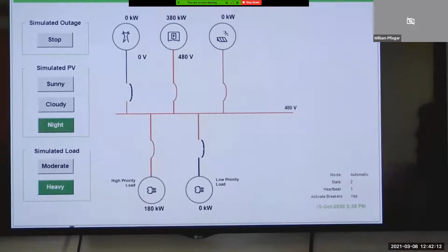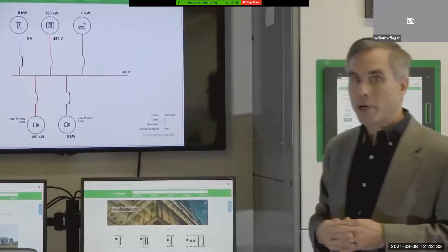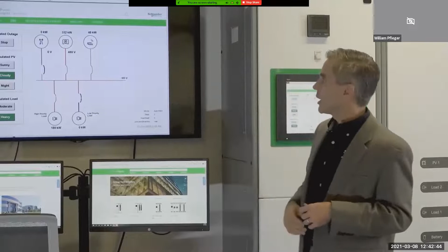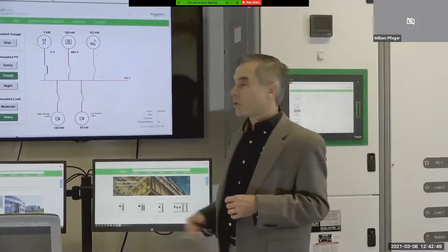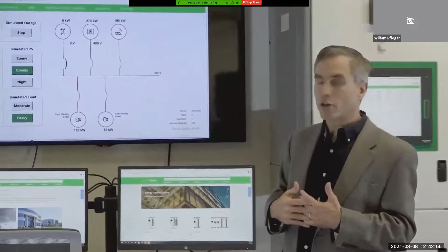And you may have even noticed that the generator for just an instant went above 400 kilowatts, and then the controller opened the low priority breaker. So we'll go ahead and see what happens if the sun were to come out. So as the solar power ramps up, notice that little clicking noise, and the system is smart enough to realize now that we're getting help from the sun, we can go ahead and close in the low priority load.